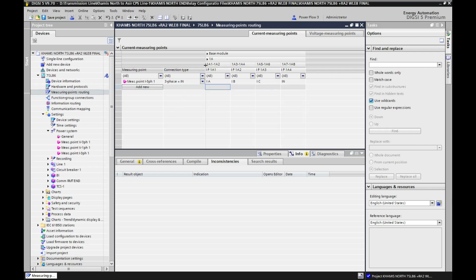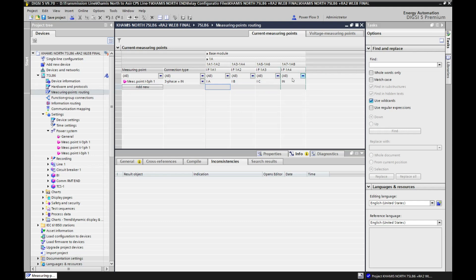Some other relays have more CT terminals available. For example, in this relay we have only one A block for CT. Some other relays also have a 1B block — 1B1, 1B2, 1B3, 1B4 — another separate terminal block hardware channel available for measuring point routing. If this is available, we can add another measuring point and connect that CT there. Some relays even have three CT block options — one A block, one B block, and one C block. It will appear here. For this 7SL86, if it had more current channels, they would be shown here when we double-click on measuring point routing.